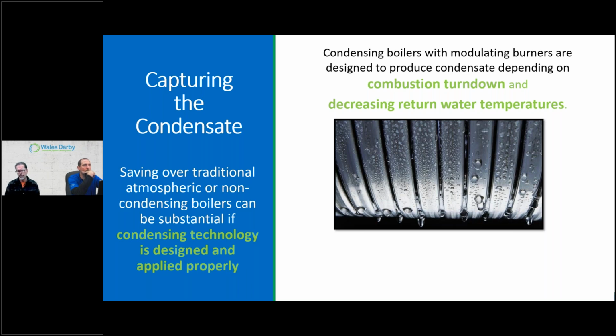So, condensing boilers with modulating burners, right? That's the engineering. We have the ability to see the change of the load because of outdoor temperatures, and now I can fire down, right? So I'm using less, but still providing the comfort needed, decreasing the return water temperature. A BTU is a BTU. I only need X amount of BTUs. Here you go, I don't need to beat it up and waste it, and then it goes up the chimney or out the flue, right? So that picture really is showing you what the end result is of a design that's making sense, right?